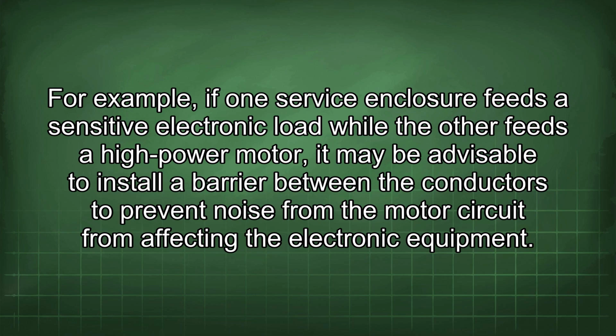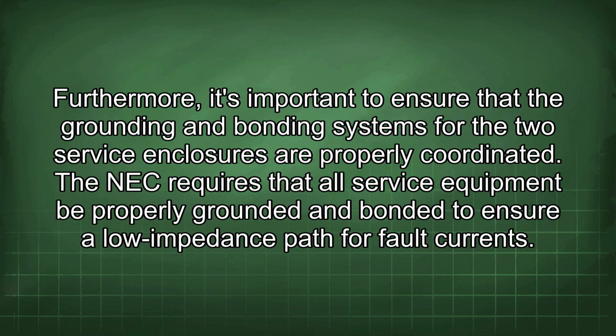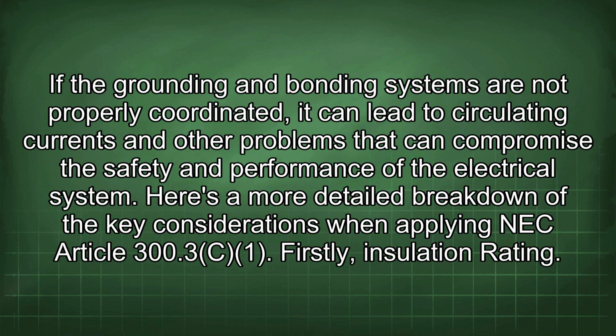For example, if one service enclosure feeds a sensitive electronic load while the other feeds a high-power motor, it may be advisable to install a barrier between the conductors to prevent noise from the motor circuit from affecting the electronic equipment. Furthermore, it's important to ensure that the grounding and bonding systems for the two service enclosures are properly coordinated. The NEC requires that all service equipment be properly grounded and bonded to ensure a low impedance path for fault currents. If the grounding and bonding systems are not properly coordinated, it can lead to circulating currents and other problems that can compromise the safety and performance of the electrical system.